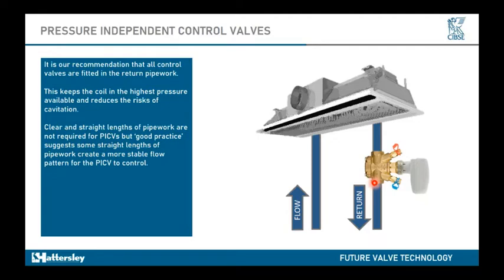You can leave them in situ when you do your flushing, but again, if you're doing a refurbishment where you're connecting to an existing system, it could be quite an old system. So again, you've got the potential of water quality issues. If you are flushing and then reintroducing it to an older system, you could potentially cause blockages, especially within the impulse tube area or that drilling. The drilling itself is only around about 3 millimetres in diameter. So again, there is the possibility of fine particles building up and blocking within that.